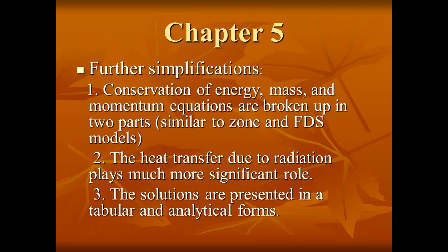Further simplifications are contained in Chapter 5. First, the conservation of energy, mass, and momentum equations are broken up into two parts, similar to zone and FDS models: conservation of energy and mass on the one hand, and the momentum equation — Navier-Stokes equations — on the other. Second, an additional simplification has been made because heat transfer due to radiation plays a much more significant role than heat transfer due to conduction and convection. Since all differential equations have dimensionless variables, the solutions are presented in tabular and analytical forms.